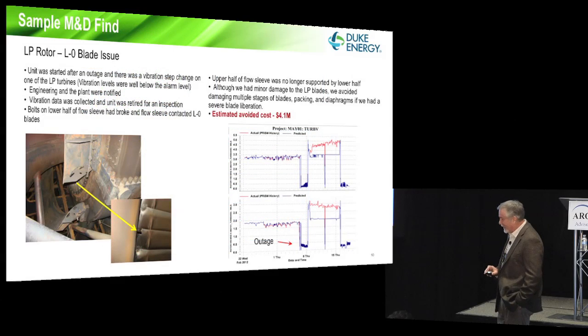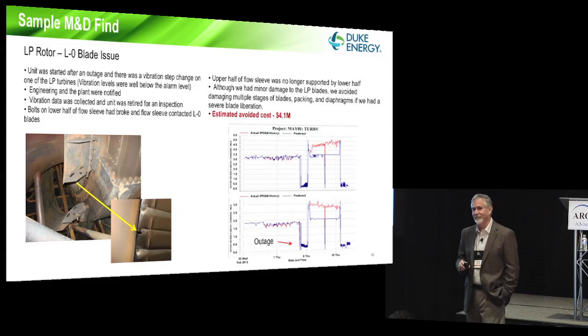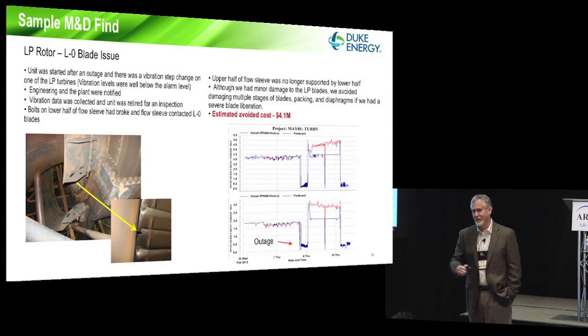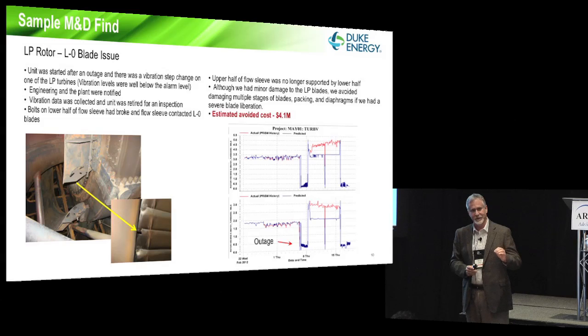One example of a find: one of our turbines, last year. We picked up small changes in vibration in the M&D center - the concept is we see it long before the operations folks do. The vibration may only move up to 5 mils, a small wiggle in the data, but we look for those small changes. That's what the Prism software does - it patterns what normal behavior is and tells you when small changes happen.